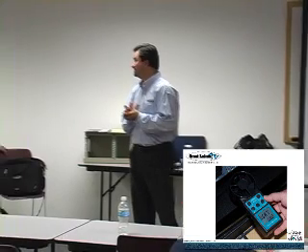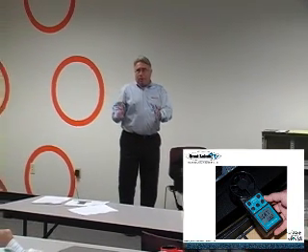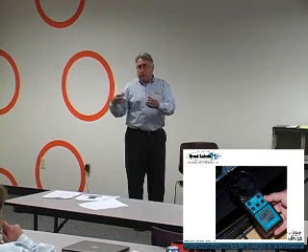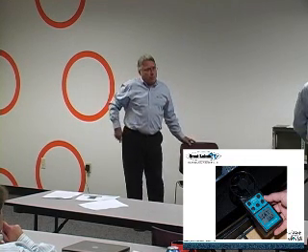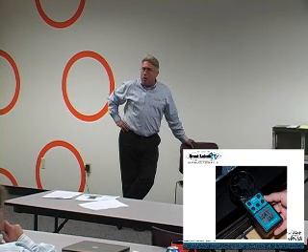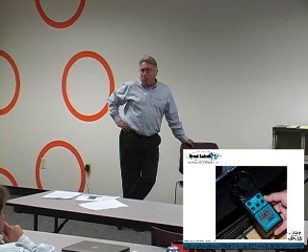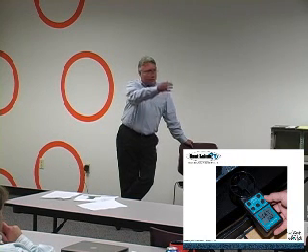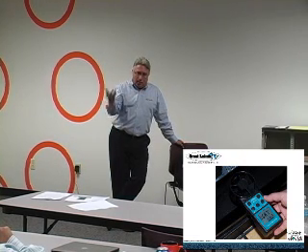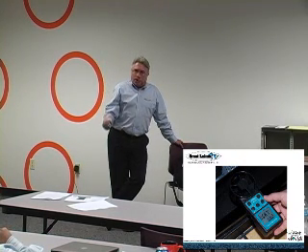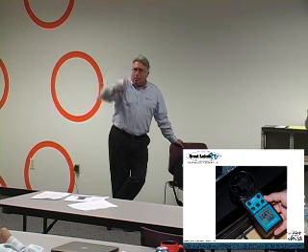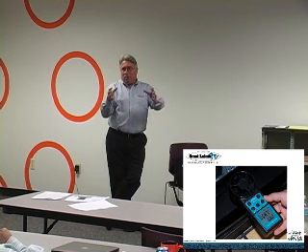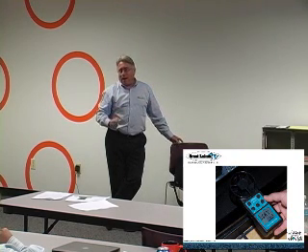And to your point, we've seen too where a cabinet with a lot of blade servers in it took all the cold air, starving everything around it. In that case, they designed it to put networking equipment near it. It was pulling well over 2,000 CFM in cold air. I think these numbers are close, but the air coming out of a floor tile is roughly 6 feet a second, and that cold air is going up. Those servers just can't capture that air that quickly.